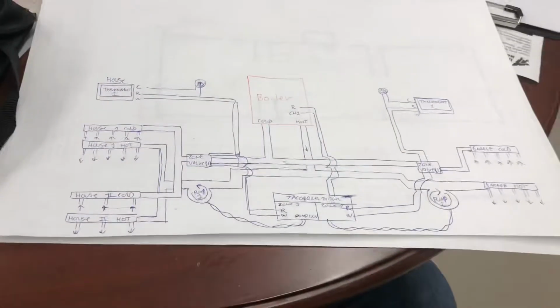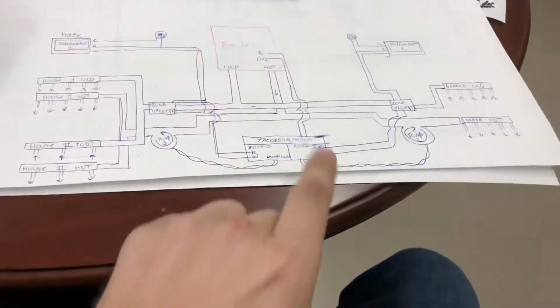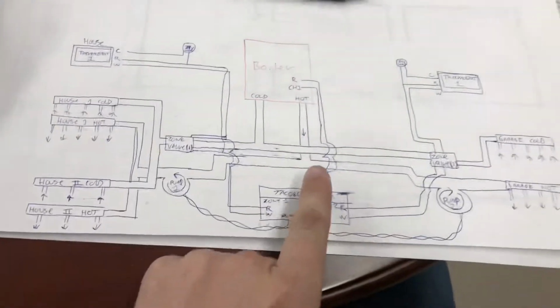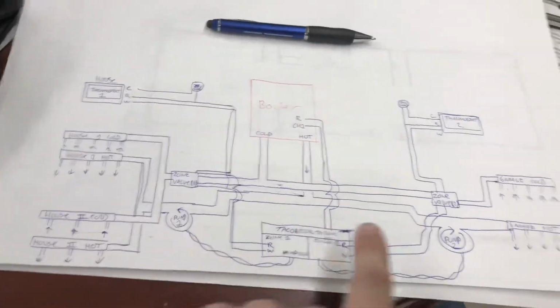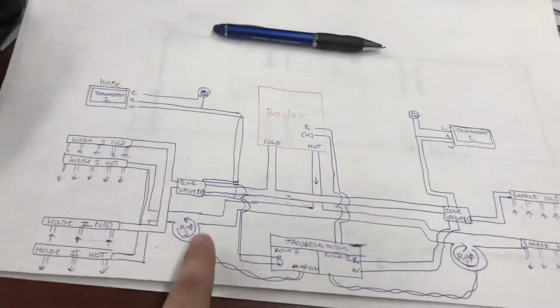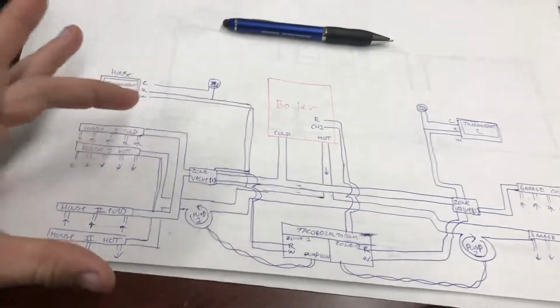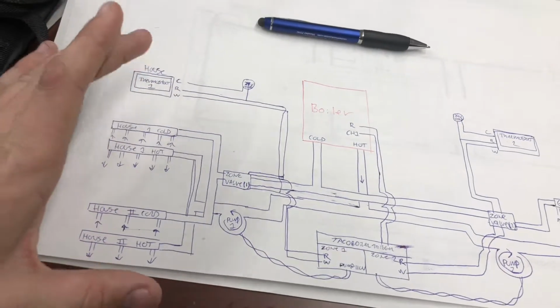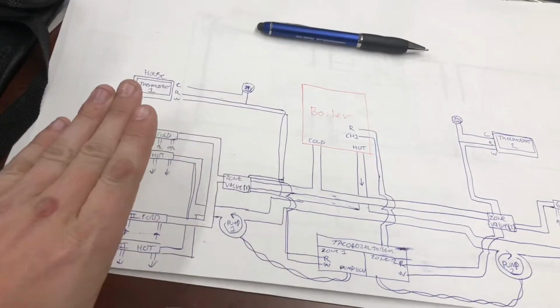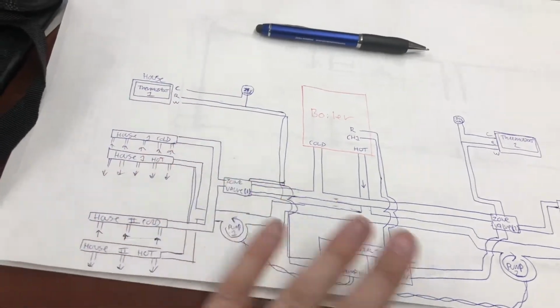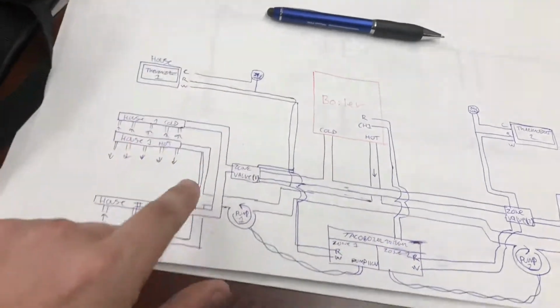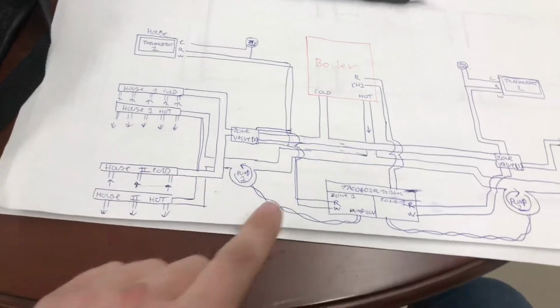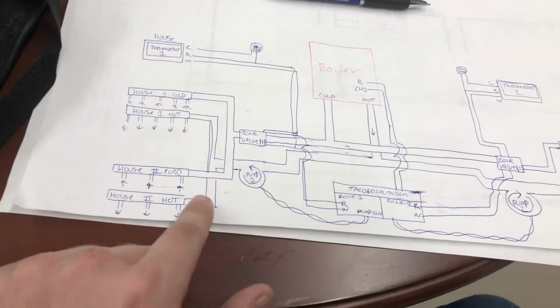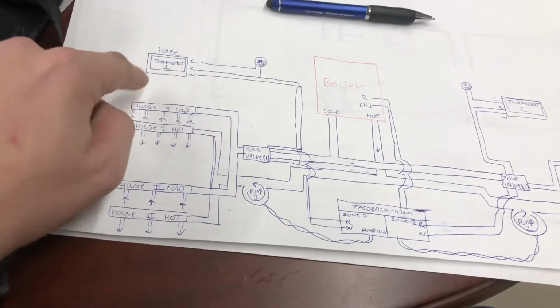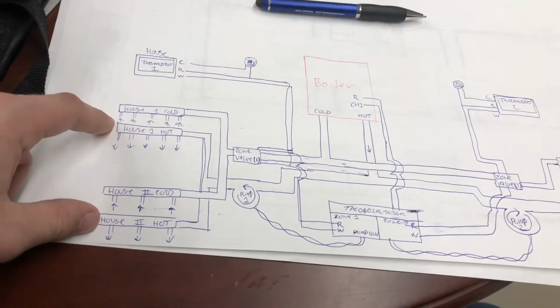So this is quick and dirty how I would probably do it at your house. So you got your hot water coming out of your boiler. That immediately feeds to both pumps, both the garage and the house pump. And this is set up just having the whole house on one thermostat. You could break this out with another zone valve and another pump and another thermostat, but just for ease of demonstration. So hot water out to the pump, then that feeds into both output manifolds, so both the hot manifolds.